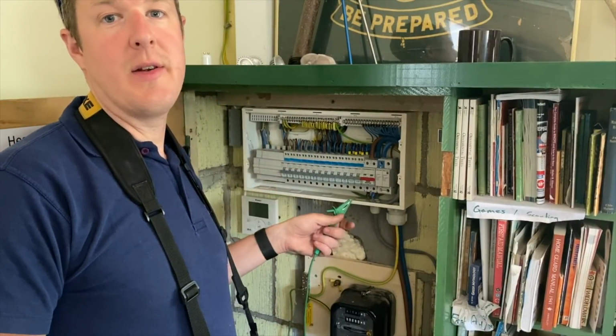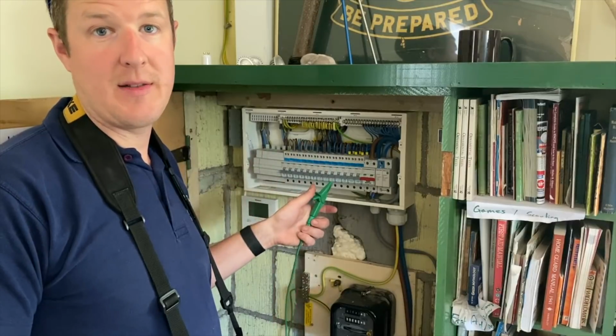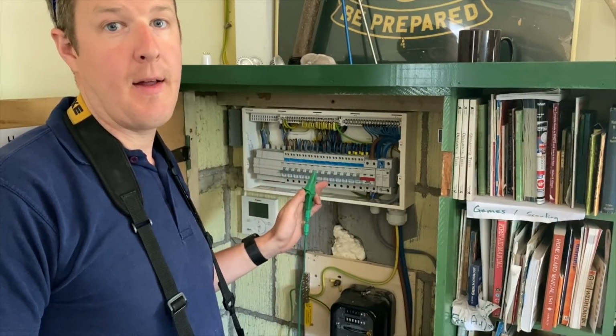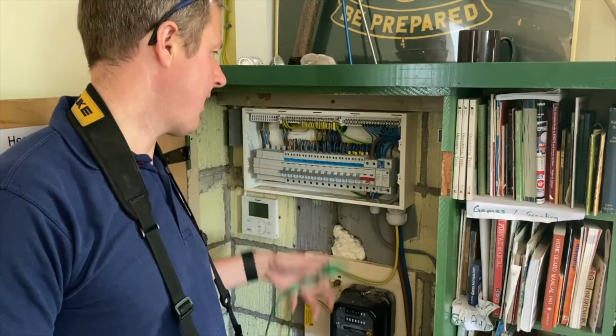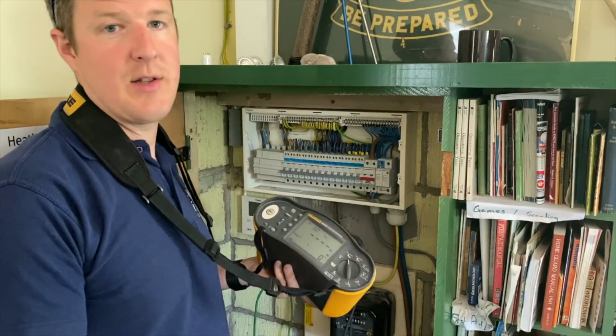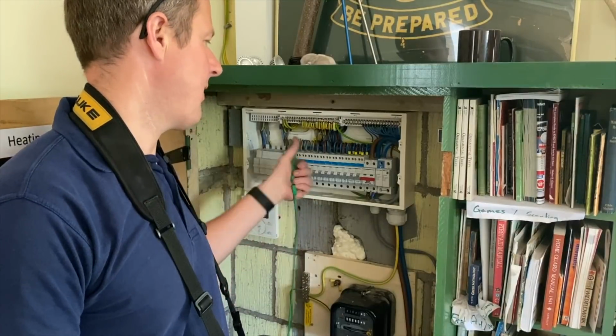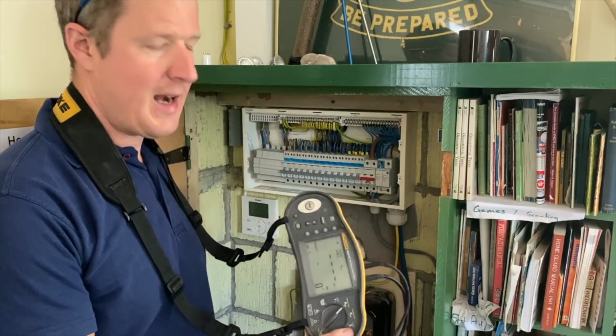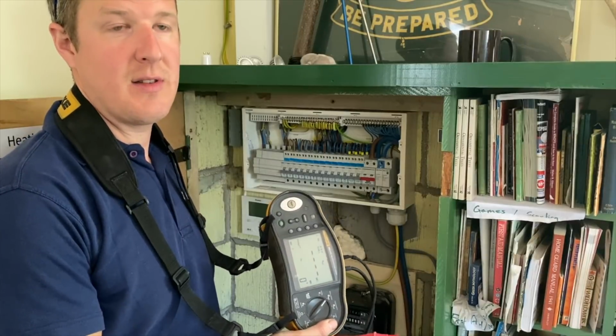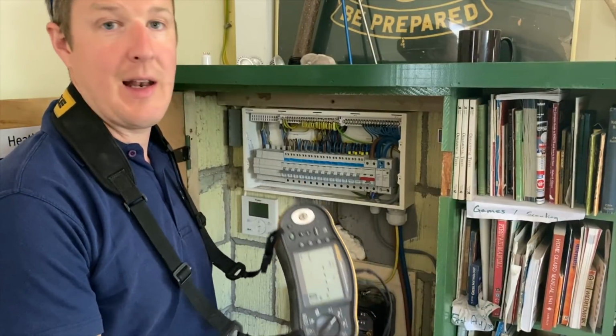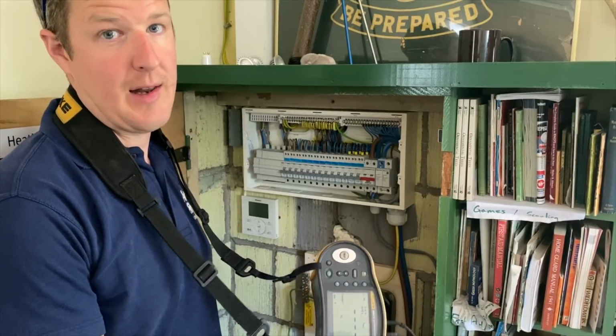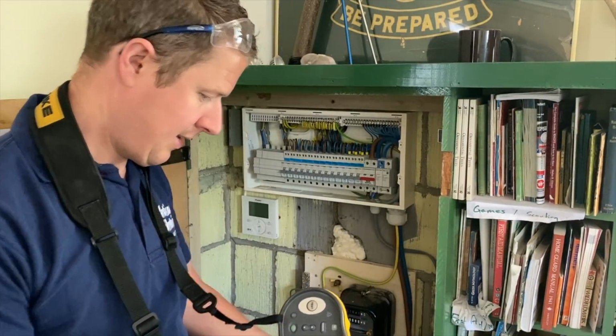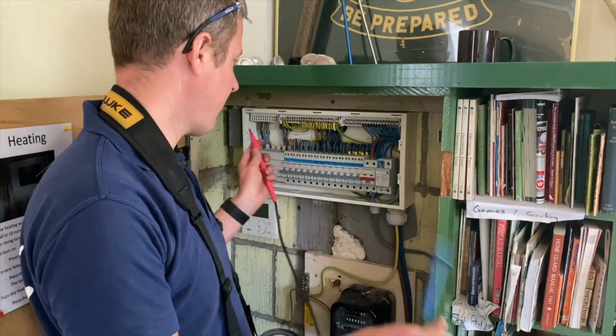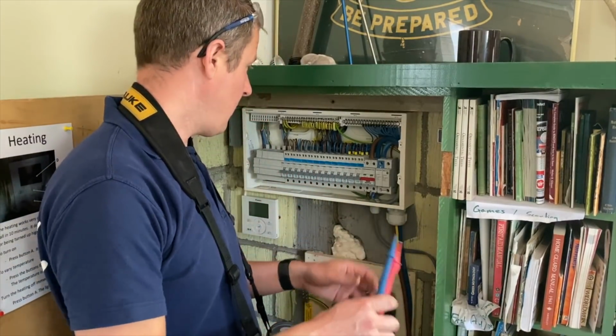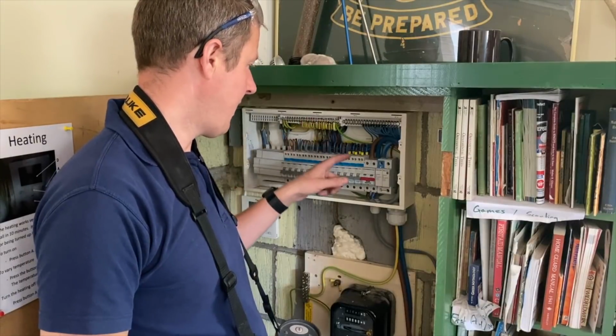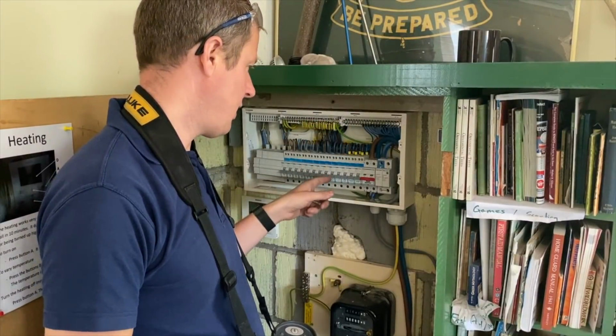Once the earth continuity readings have been verified throughout the property so that you know that everything is earthed properly, then it's safe to start energizing the circuits using insulation resistance testing. So we don't actually turn the circuits on yet, but first we put energy into the circuits using our insulation resistance tester to make sure that the insulation of the cables is up to scratch and there aren't any short circuits throughout the installation. So we do several tests for insulation resistance. We do live to earth, neutral to earth, and live to neutral.